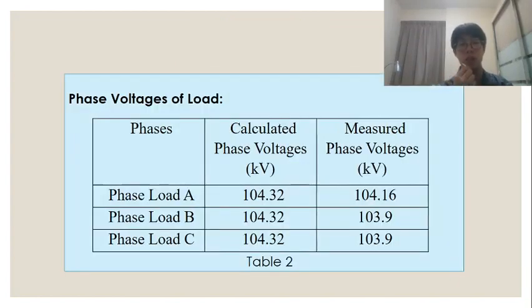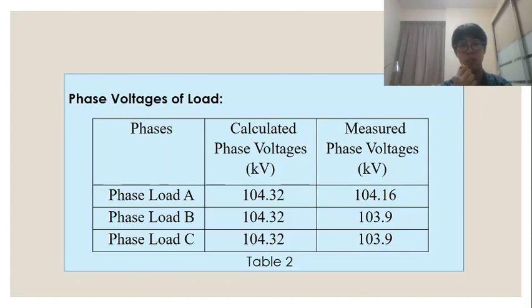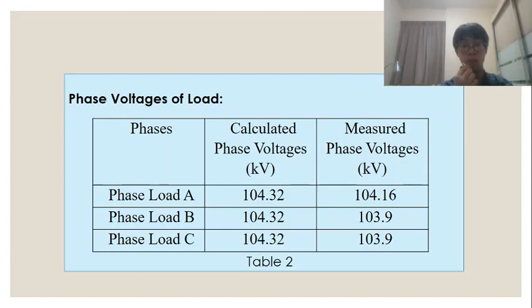Table 2 shows the phase voltages of the load. The calculated phase voltages for phase load A, phase load B, and phase load C are the same, at 104.32 kV. There is a slight difference between the calculated and measured phase voltages. The measured value for phase load A is 104.16 kV, and the measured values for phase load B and C are both 103.9 kV.